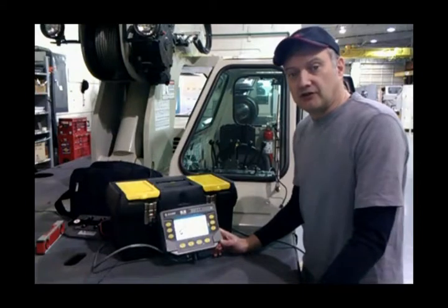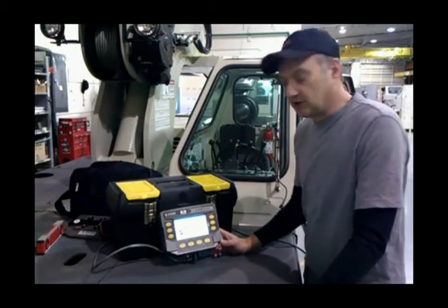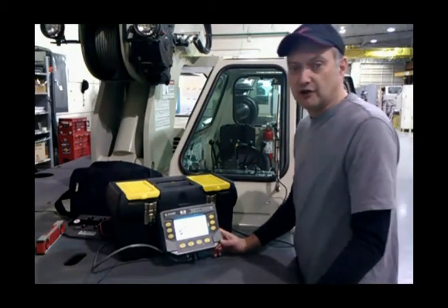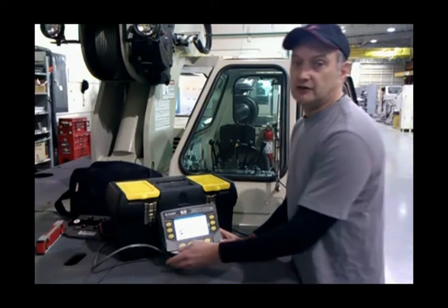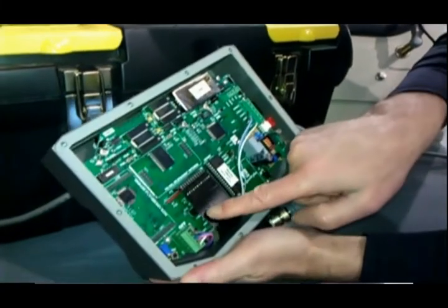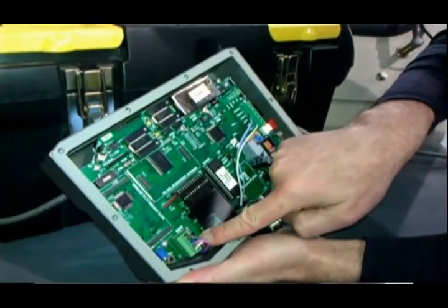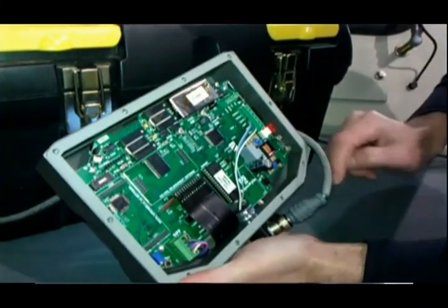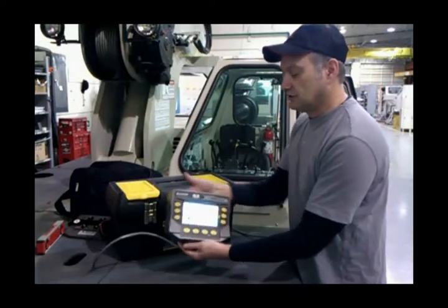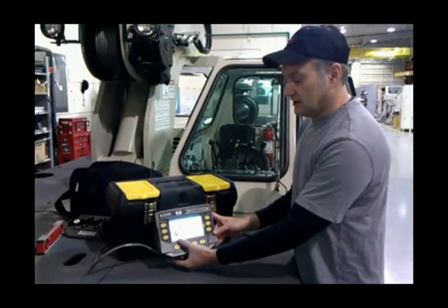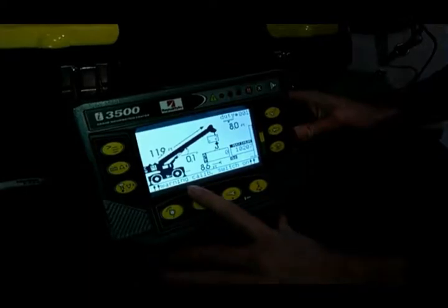Whenever we adjust a sensor, whenever we recalibrate a sensor, we need to get the console into calibration mode. Basically what we need to do is remove the rear cover and come to the lower left-hand corner, and there's a switch down here for calibration. You need to go ahead and turn that on. And what you'll notice on the screen once you've done that is it now says warning, calibration switch on.